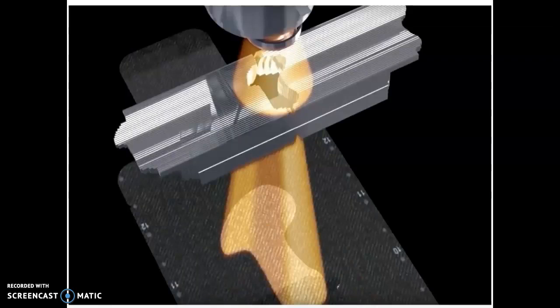And so linear accelerators actually have these tungsten plates, and they can move freely. As this linear accelerator rotates around a patient who is sitting on a stationary bed, these tungsten plates move and absorb the part of the radiation that we don't want to hit the patient, and it can create this outline of the patient's tumor. So as this moves around the patient, it can change shape so that it's always hitting the patient's tumor and avoiding the healthy tissue.